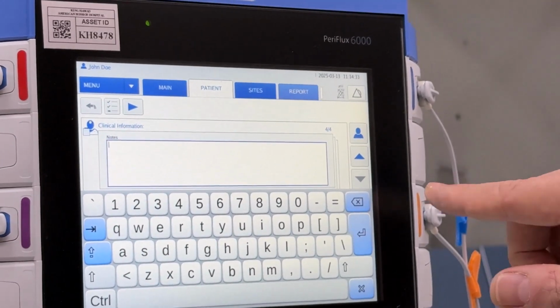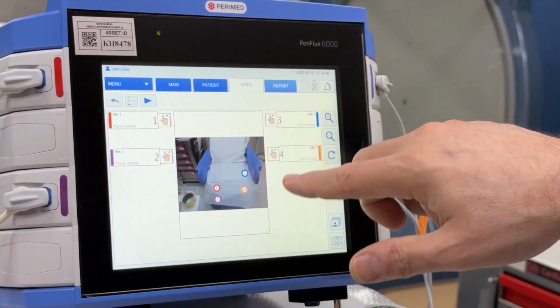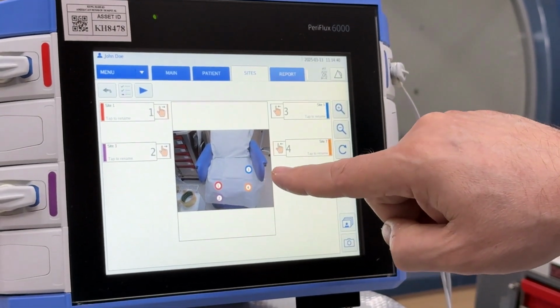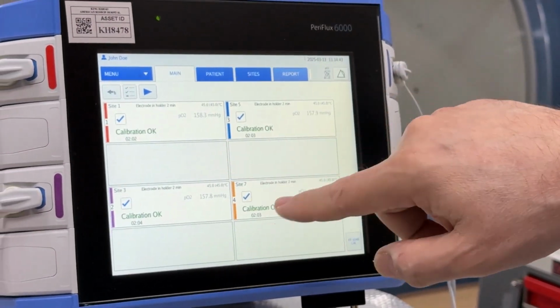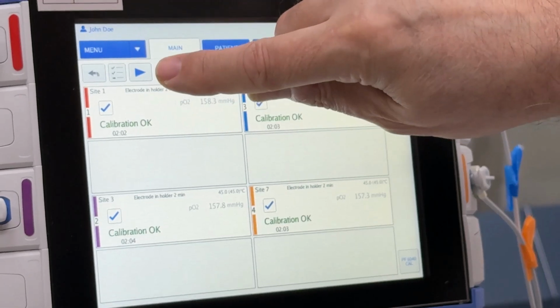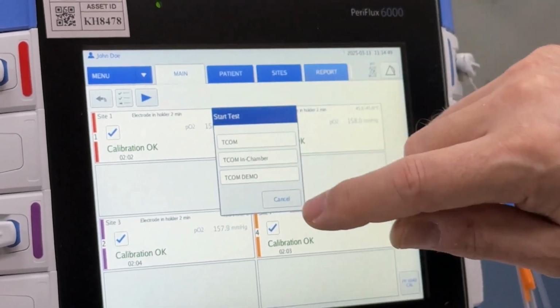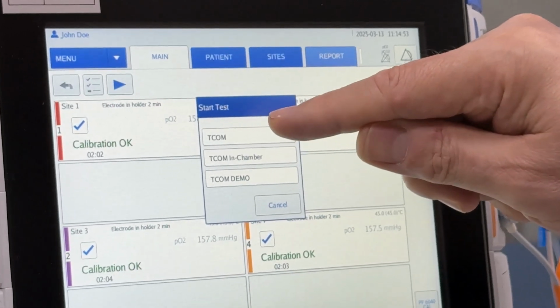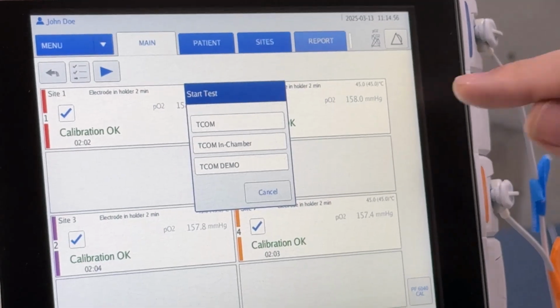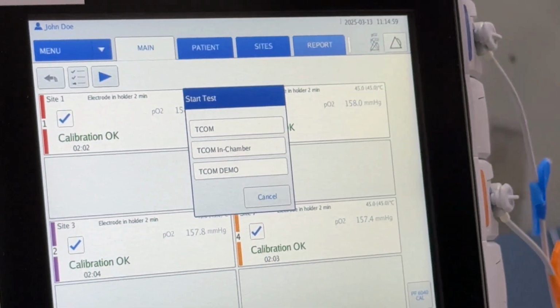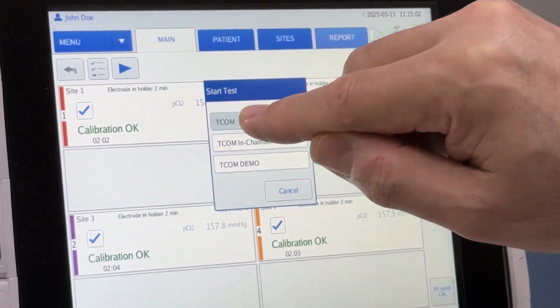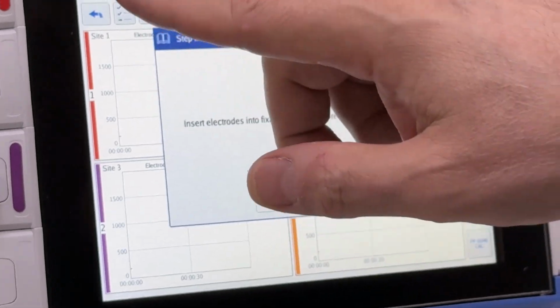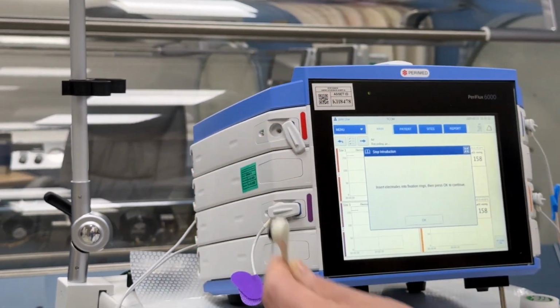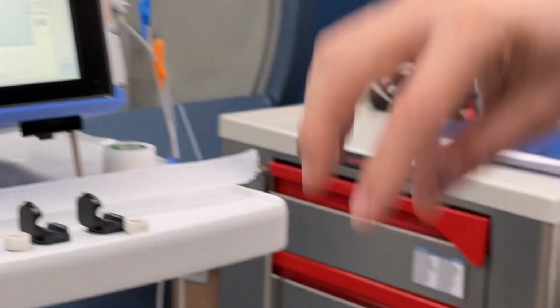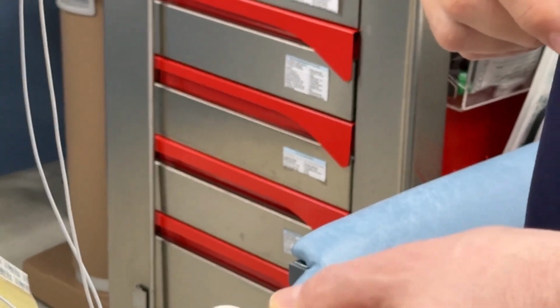So at this point, we have the patient's wounds identified and marked in terms of the electrode sites. And now we know that the electrodes are calibrated, and this play button is the one that starts the test. It will prompt you, and mostly we use the top one, which is transcutaneous oximetry outside of the hyperbaric chamber. The second one is only used if the TCOM is done inside the hyperbaric chamber. So we push TCOM there, and then it prompts you to put the electrodes in the various rings. In the meantime, you will have prepared the site where you are going to place the electrode on the patient, and we're going to show you that with a separate video.